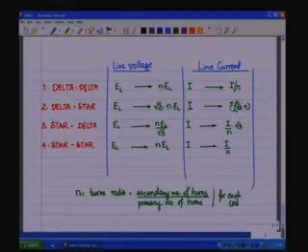The phase current in the case of the delta star is going to be I by root 3 n, but on the primary side the phase coils will be rated at I by root 3 rather than I, and therefore the primary side phase coils can have a smaller gauge. So, one could argue along these lines and suitably rate and pick the proper topology of the transformer for a particular application. We stop here and continue in the next class.